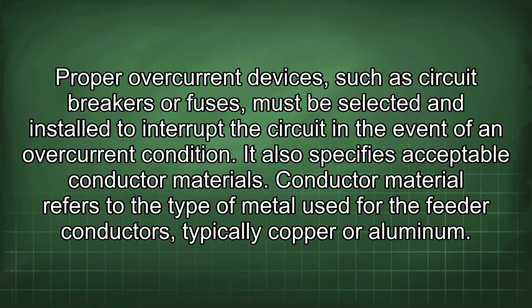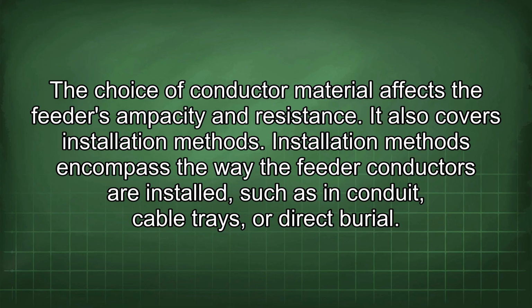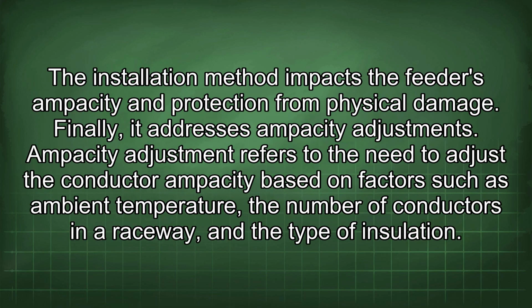It also specifies acceptable conductor materials. Conductor material refers to the type of metal used for the feeder conductors, typically copper or aluminum. The choice of conductor material affects the feeder's ampacity and resistance. It also covers installation methods. Installation methods encompass the way the feeder conductors are installed, such as in conduit, cable trays, or direct burial. The installation method impacts the feeder's ampacity and protection from physical damage.